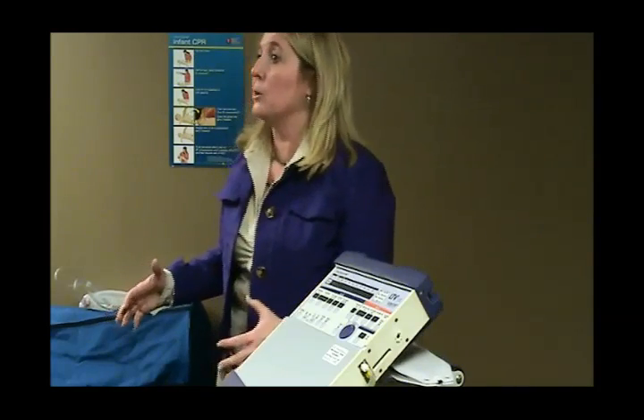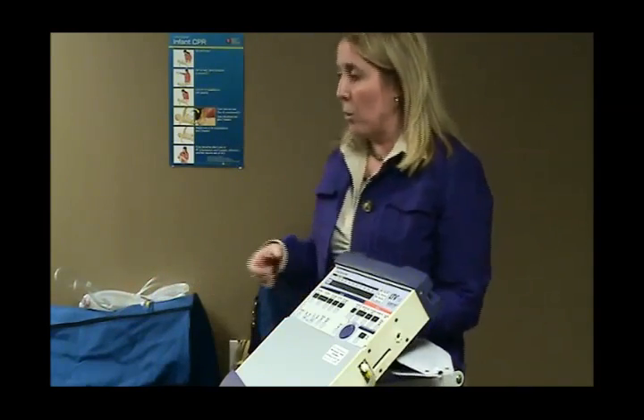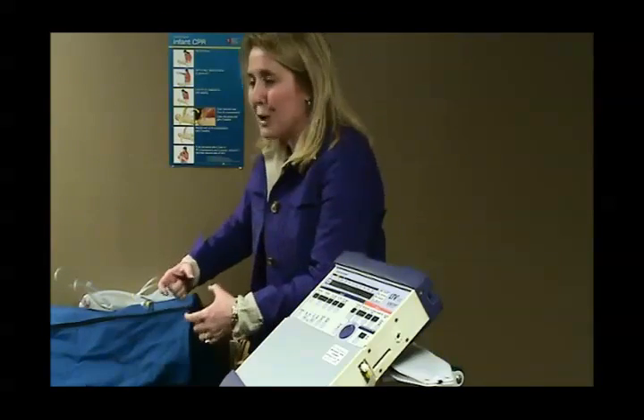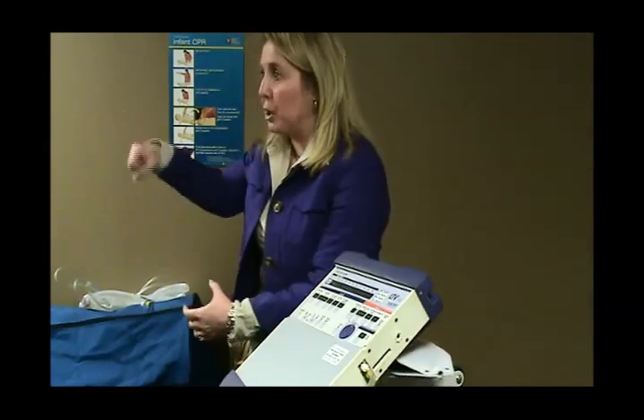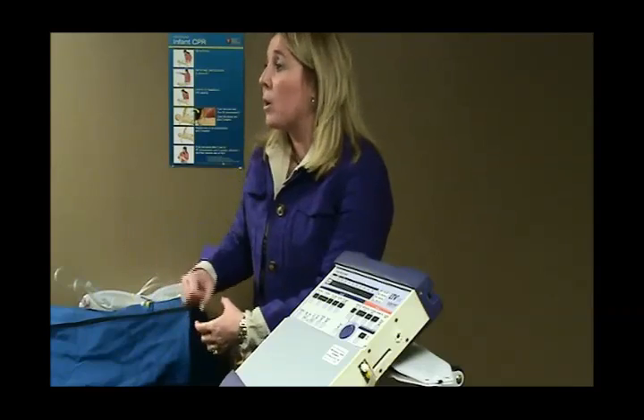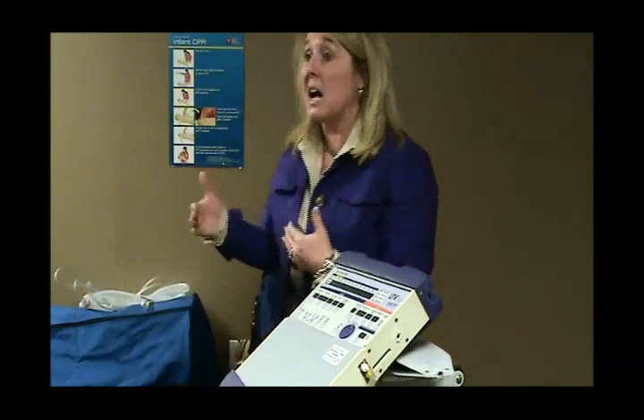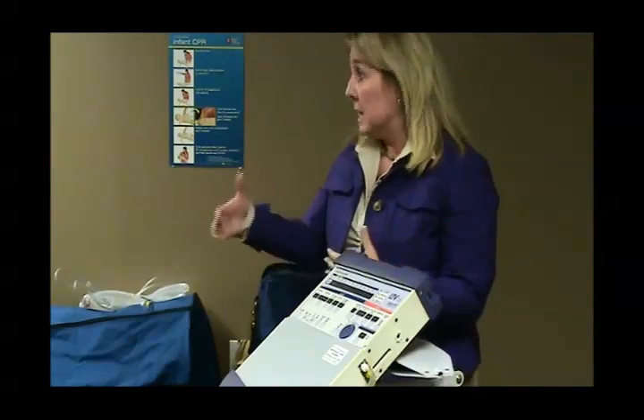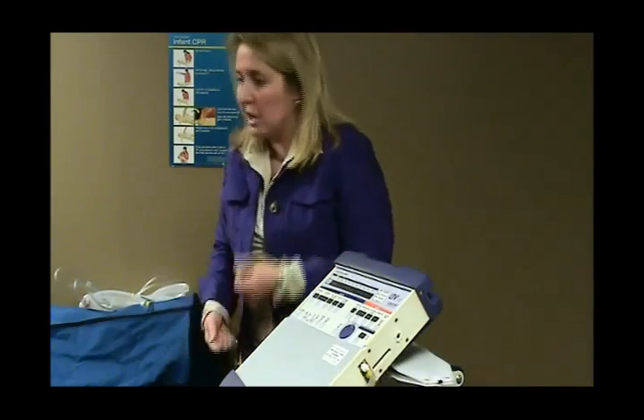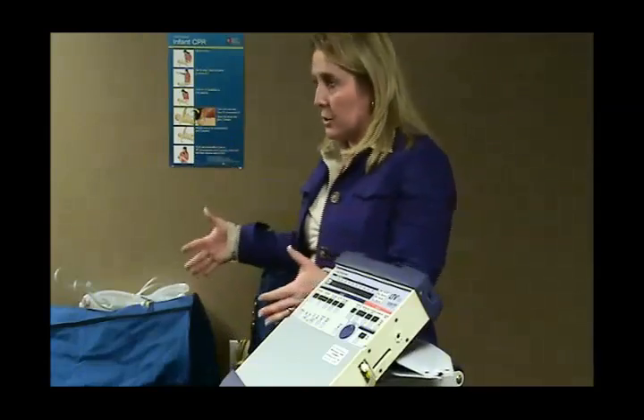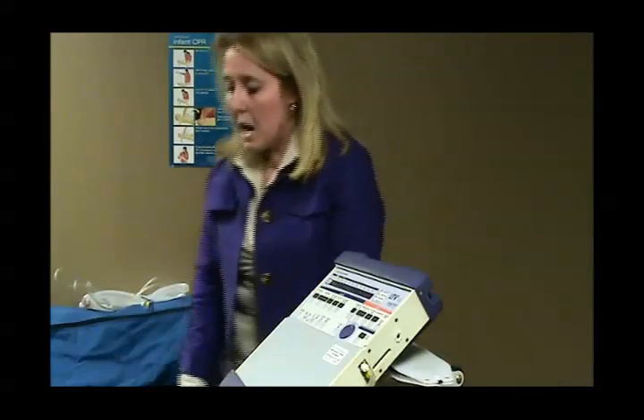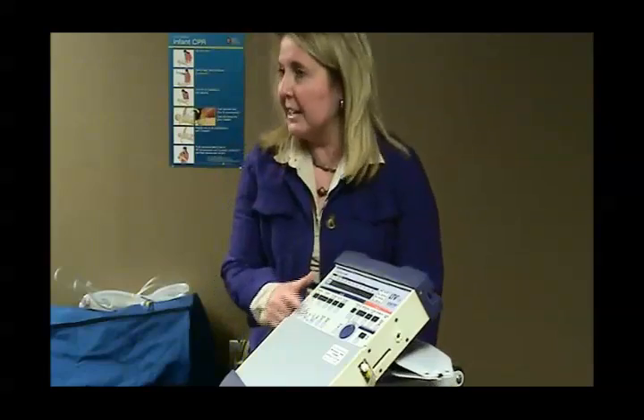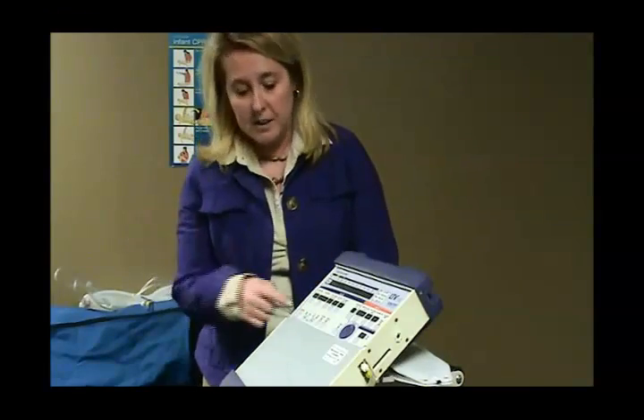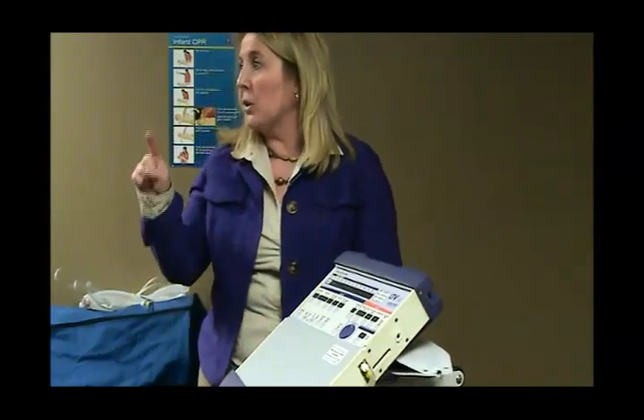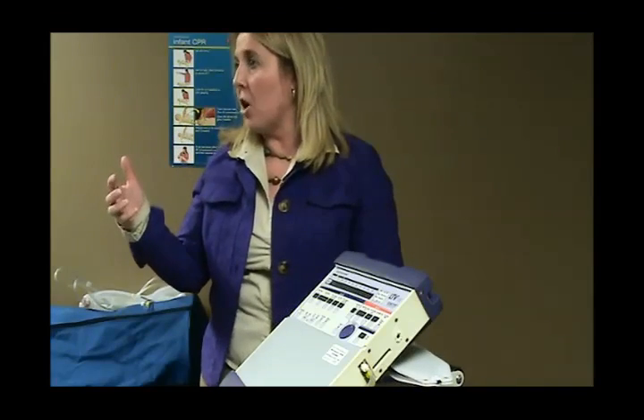Sometimes they also use those if there's no generator in the home, because they can actually have a power strip on them, if you've seen that one, because then you can plug your portable suction into it. So if the power goes out, it allows them more time in a disaster type situation, like a bad ice storm or something, because you've got the ability to run your suction and your ventilator and a pulse ox off of it. Okay? So your first button, again, on standby, you press it to turn it on, you press it to turn it off. Press and hold it for 3 full seconds and it'll shut the ventilator off.